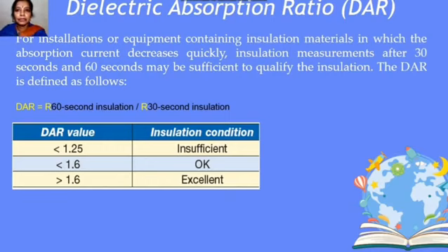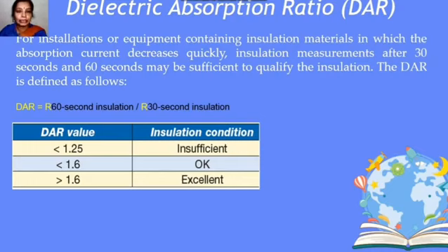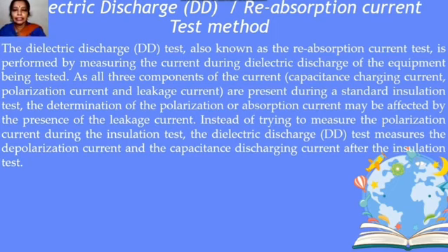The Dielectric Absorption Ratio (DAR) test is used for insulation materials where absorption decreases quickly. Insulation measurements after 30 seconds and 60 seconds may be sufficient. DAR = R60s / R30s. If DAR is less than 1.25, insulation condition is insufficient; if between 1.25 and 1.6, it is acceptable; if greater than 1.6, it is excellent.